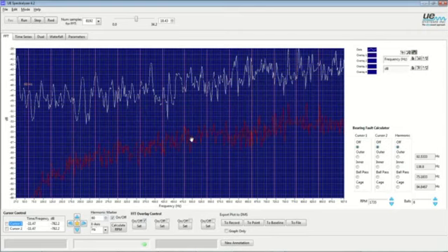And this is a little bit different than the first recording in that we don't have this peak on 120 like we did before. However, there's one out here at 240 hertz. And as we come further out the line, the shifts are off of the harmonic and nothing's really hitting right on it. However, the other similarity that I see here that I would focus in on is the activity or frequency noise in between each of the harmonics.